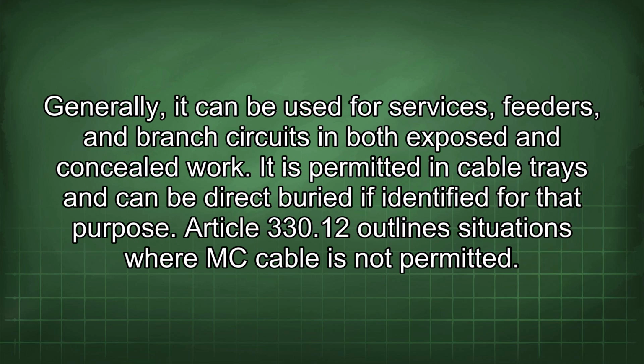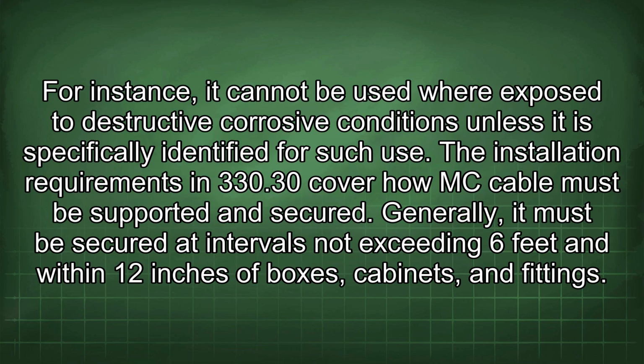Generally, it can be used for services, feeders, and branch circuits in both exposed and concealed work. It is permitted in cable trays and can be direct buried if identified for that purpose. Article 330.12 outlines situations where MC cable is not permitted. For instance, it cannot be used where exposed to destructive corrosive conditions unless it is specifically identified for such use.